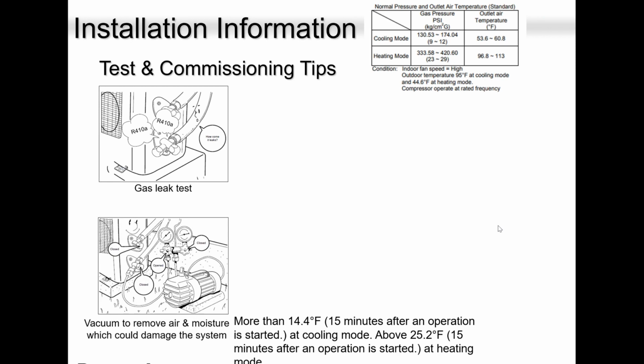Vacuum. Always vacuum the system down to 300 microns. Most of the guys on a 10 to 20 feet run of piping, they get down to 150, 180. So please, good vacuum means good job. Good job means no complaints. No complaints means more jobs, more projects, and you're growing and growing.